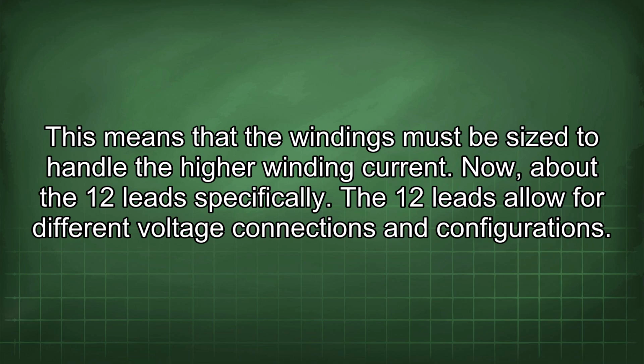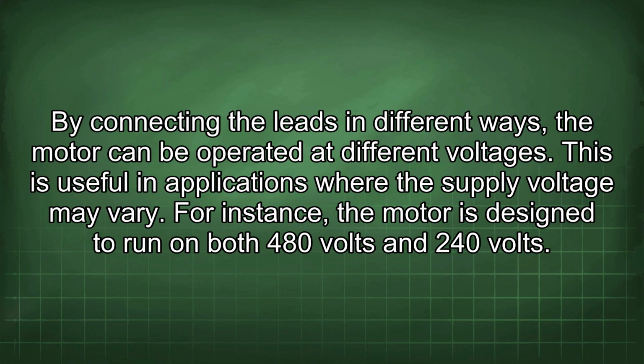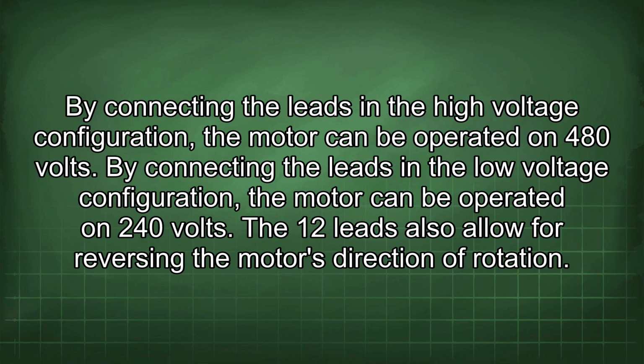Now about the 12 leads specifically. The 12 leads allow for different voltage connections and configurations. By connecting the leads in different ways, the motor can be operated at different voltages. This is useful in applications where the supply voltage may vary. For instance, the motor is designed to run on both 480 volts and 240 volts. By connecting the leads in the high voltage configuration, the motor can be operated on 480 volts. By connecting the leads in a low voltage configuration, the motor can be operated on 240 volts.